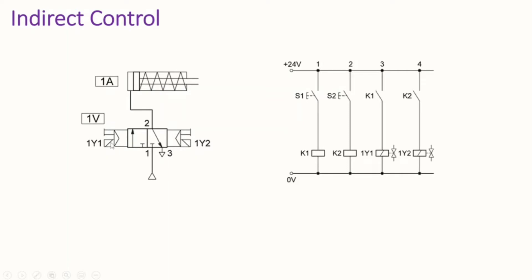Whenever we turn on — push — switch S1, current passes through the line, K1 is energized, and from there we close make switch K1. Therefore current will pass to solenoid 1Y1, it is energized, and we will have this valve electrically actuated, right-shifting to the second position. Air will pass and we will have the pressure needed to overcome the spring force inside the cylinder, resulting in the piston advancing.